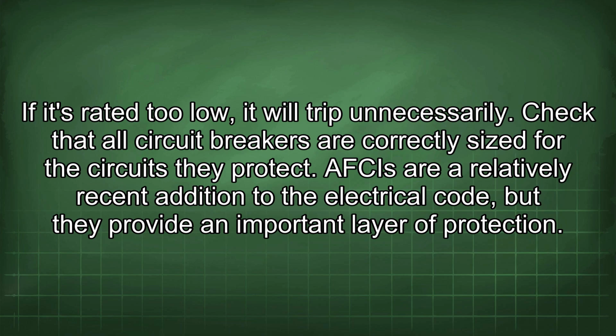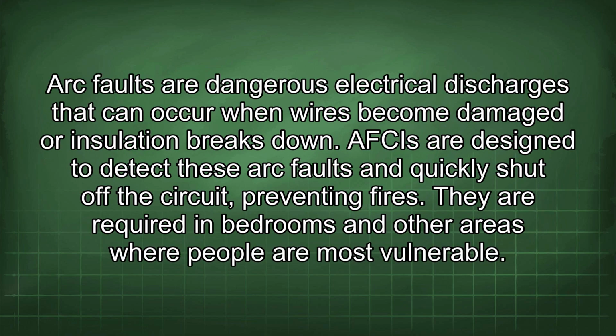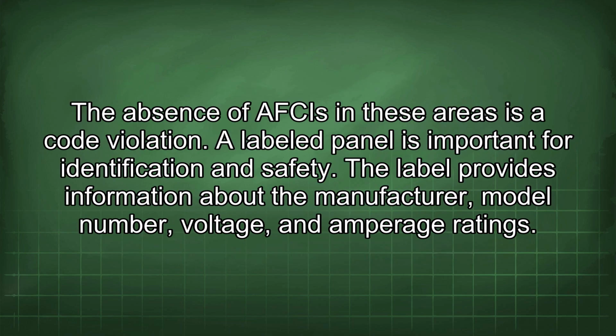AFCIs are a relatively recent addition to the electrical code, but they provide an important layer of protection. Arc faults are dangerous electrical discharges that can occur when wires become damaged or insulation breaks down. AFCIs are designed to detect these arc faults and quickly shut off the circuit, preventing fires. They are required in bedrooms and other areas where people are most vulnerable. The absence of AFCIs in these areas is a code violation.